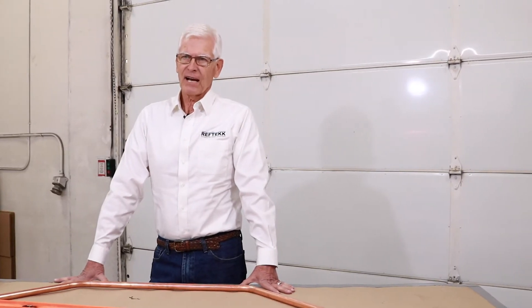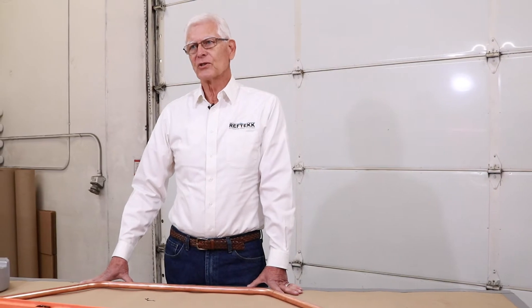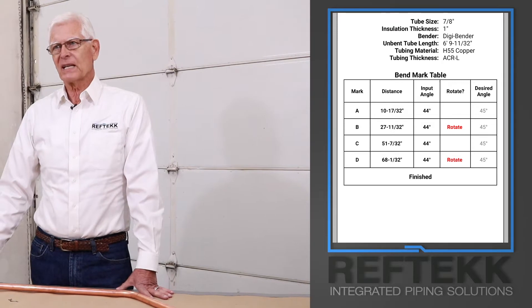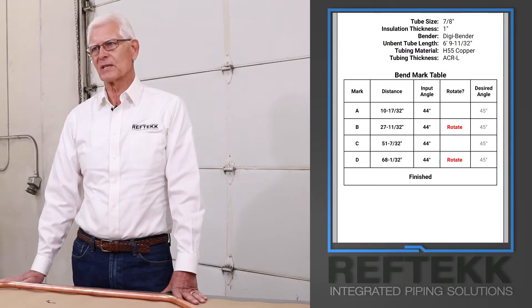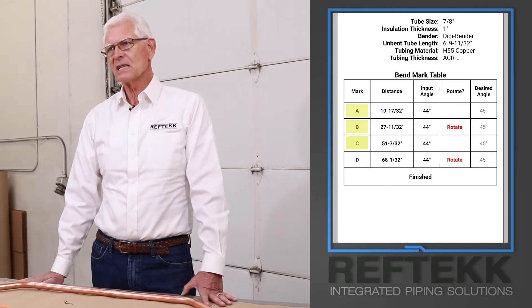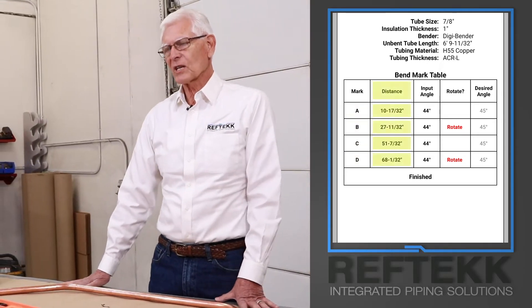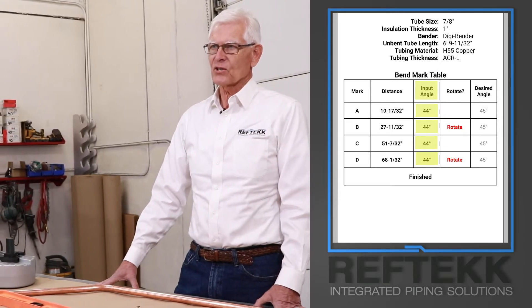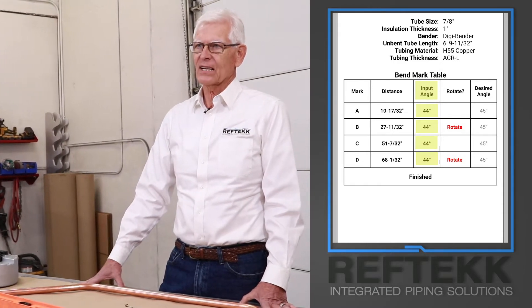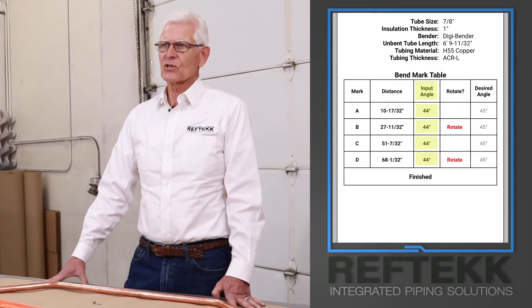Start with the correct type of tube. Remember, both soft copper O60 or half hard copper H55 can be bent. Do not bend H58 hard copper. Ensure the tube is long enough to make all of the bends — the output from the Reftekk bending app shows the minimum length required for the initial unbent tubing. The bending app output shows four reference points labeled A, B, C, and D. These are the starting points for each bend. The distance column shows the distance to each mark from a single starting point. The input angle column shows the angle the bender's LCD display should be set to. You may notice the input angle is not the same as the desired angle — the input angle compensates for type of material and spring back, allowing the bender to create bends close to the desired angle.